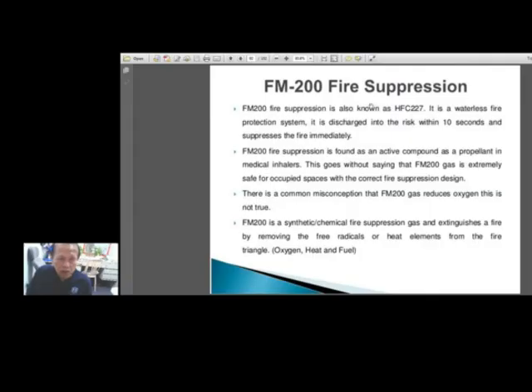So the FM200 fire suppression, also known as HFC227, is a waterless fire protection system. It is discharged in the room within 10 seconds and suppresses the fire immediately. FM200 is also found as an active compound, as a propellant in medical inhalers. This goes without saying that FM200 gas is extremely safe for occupied spaces with the correct fire suppression design.